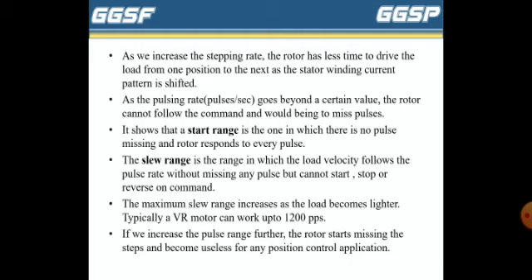is the range in which the load velocity follows the pulse rate without missing any pulse but cannot start, stop or reverse on command. The maximum slew range increases as the load becomes lighter. Typically a VR motor can go up to 1200 pps.